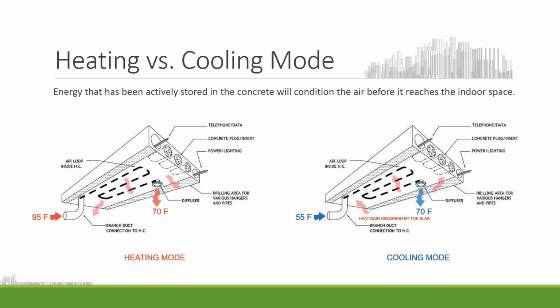This shows an inset diagram of a modified hollow core slab. Once again, this is the labyrinth within the hollow core slab where it comes in from the HVAC system and exits into the building space with a standard diffuser. Please note that in heating mode or cooling mode, the temperature of the air that is coming through the slab gets conditioned by the stored energy that's in the concrete, and it comes out at the desired temperature of the room. So we're not forcing air out that's 95 degrees to mix with 60-degree air to get your comfortable temperature. We're actually conditioning the air before it comes into the room, and it's coming out into the room at the temperature that is desired for comfort of the occupants.